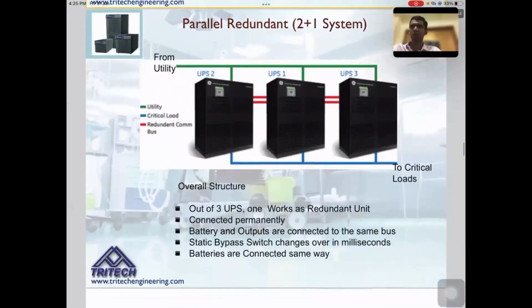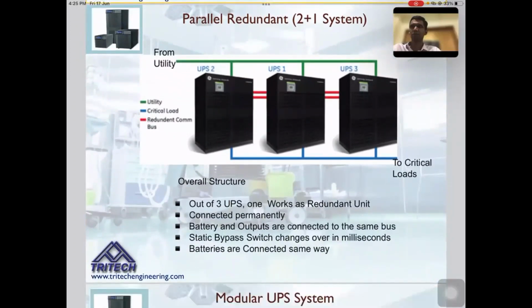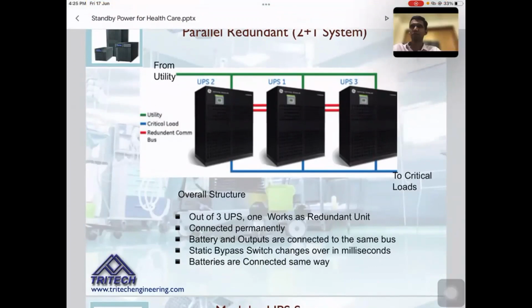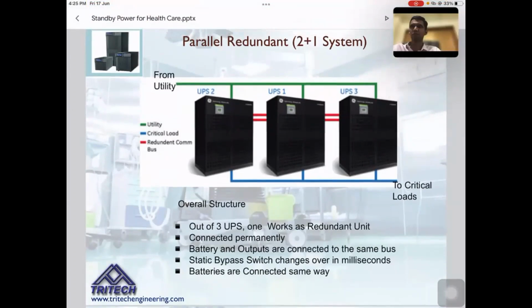What I'm showing you right now is the parallel redundant system, which has two UPS systems working and one standby, and these are connected permanently, with batteries and outputs connected to the same bus. Again, static bypass switches are provided, which can change over in a few milliseconds. This configuration is used only for conventional UPS systems. So basically, you have equal size UPSs connected to work, plus N+1. This is the general configuration we have had until now. Maybe 10 years back also this system was there.